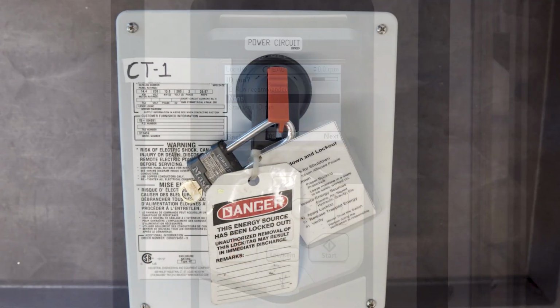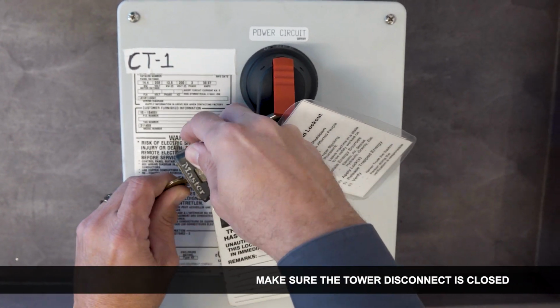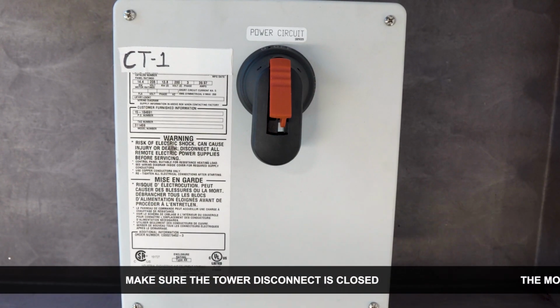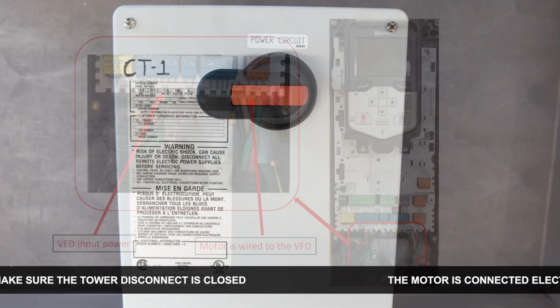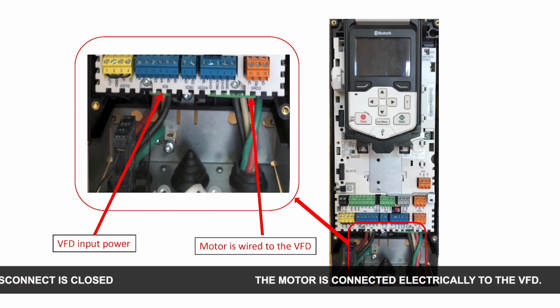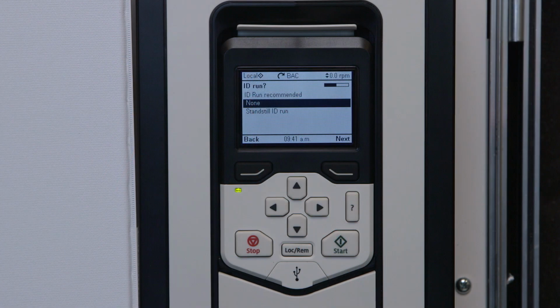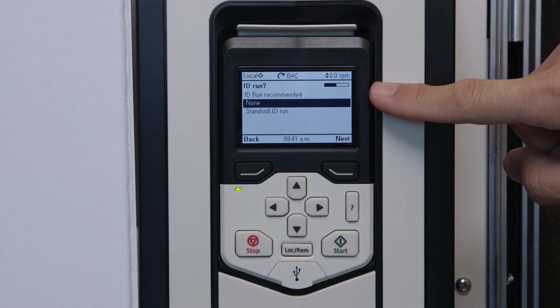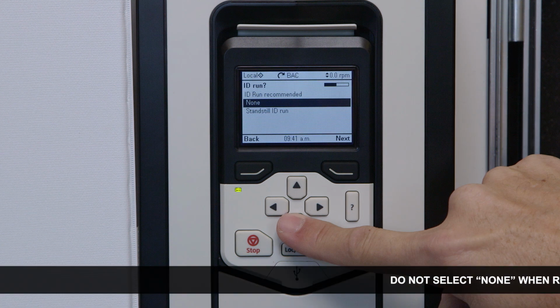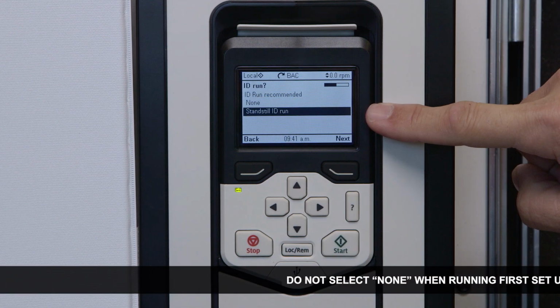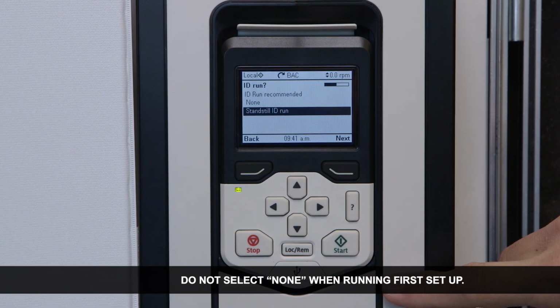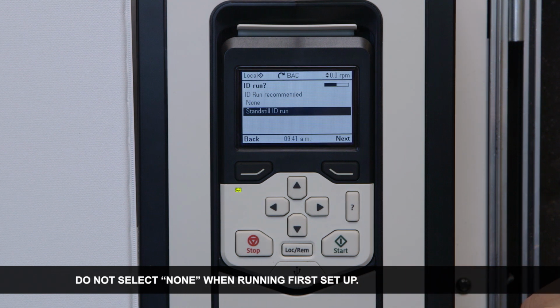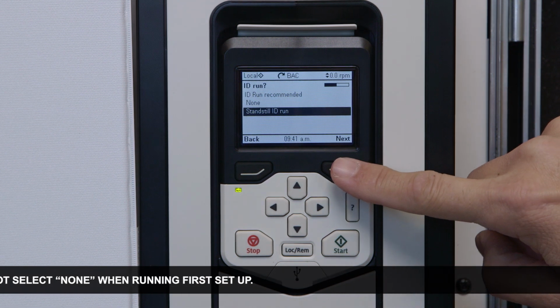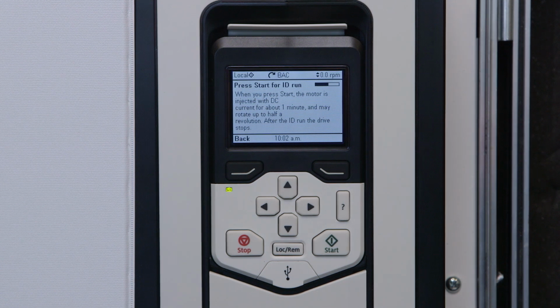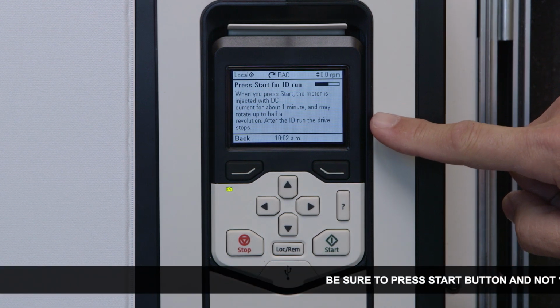Now, let's set up the motor ID run. First, check to ensure you are in mode for ID run. Before we begin, we need to make sure the tower disconnect is closed and the motor is connected electrically to the VFD. Now, reconfirm that you are in ID run mode. Scroll to highlight Standstill ID Run. You can select None only if you are running through the setup for a second time. Press Next.